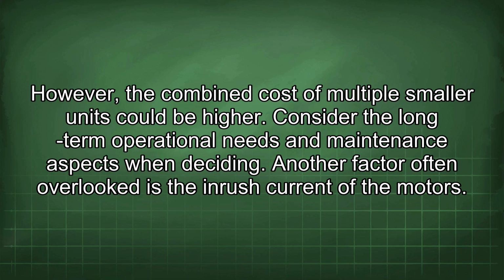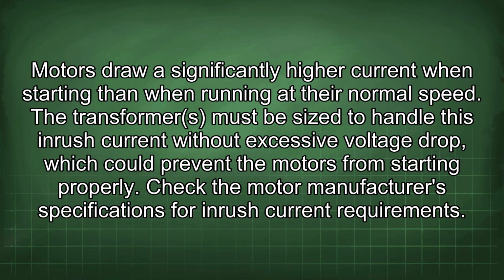Another factor often overlooked is the inrush current of the motors. Motors draw a significantly higher current when starting than when running at their normal speed. The transformers must be sized to handle this inrush current without excessive voltage drop, which could prevent the motors from starting properly. Check the motor manufacturer's specifications for inrush current requirements.